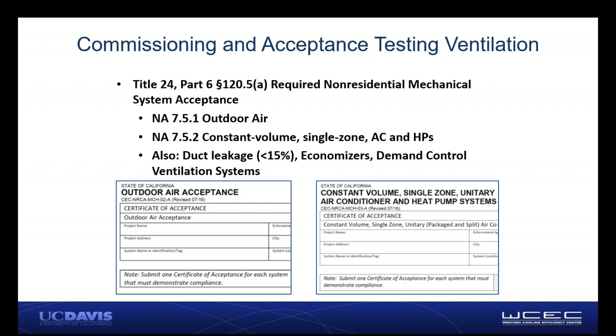That's why we believe we see so many of these problems in recently installed systems, because essentially this is like your last defense. If you go to do the acceptance test and it fails, you know something went wrong—either the wrong equipment was purchased, it wasn't installed correctly, the damper wasn't set correctly, whatever.